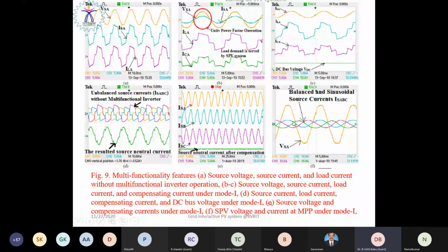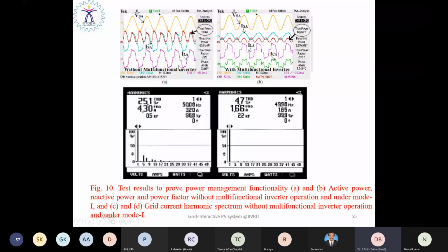And this is for the active power sharing. It also contributes to active power sharing, because the inverter is powered by a solar PV. So it also supplies additional power to the grid, so that the load demand can be met not only by the grid, but also by the PV. So it also contributes to active power sharing.